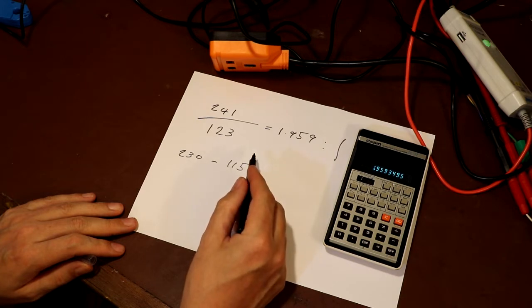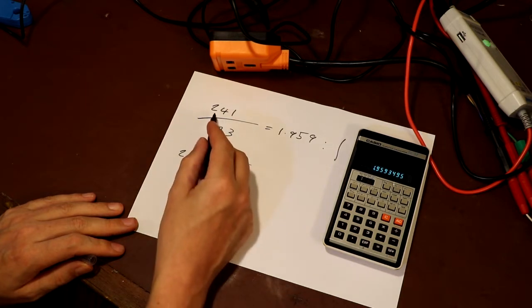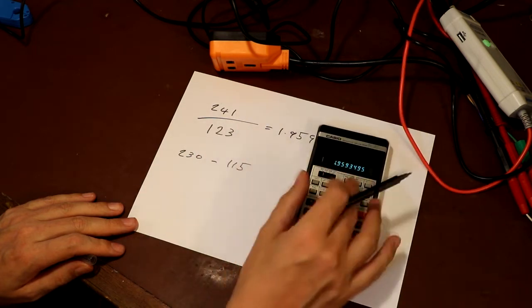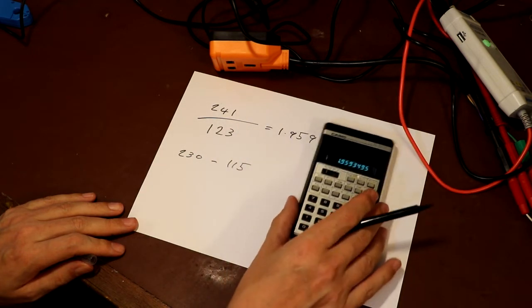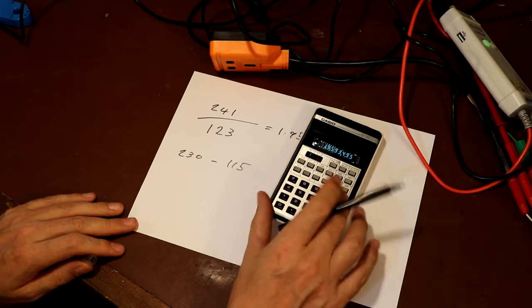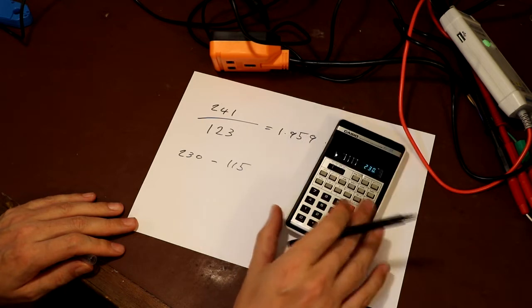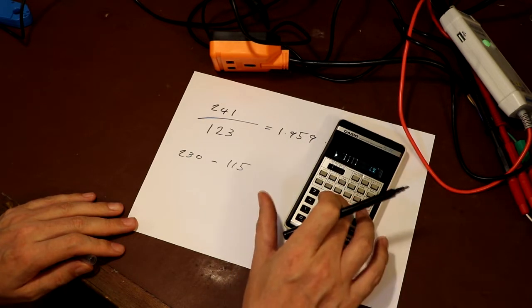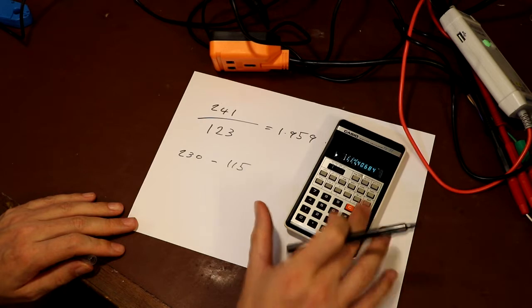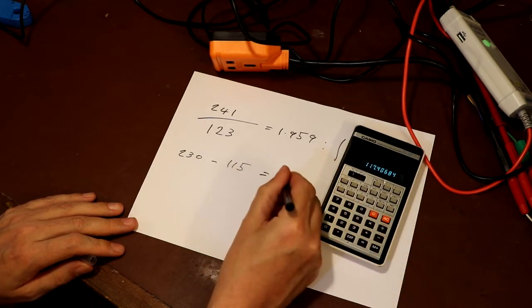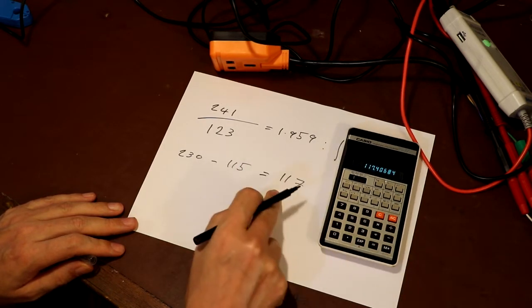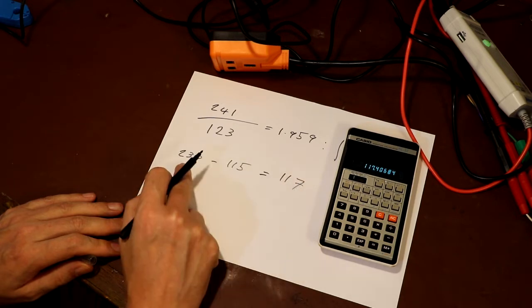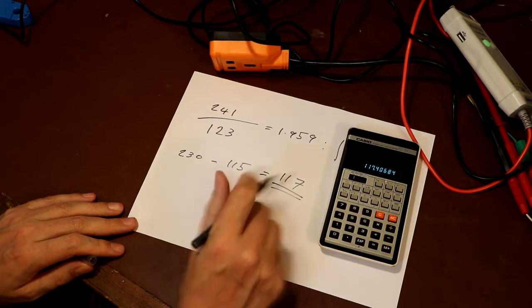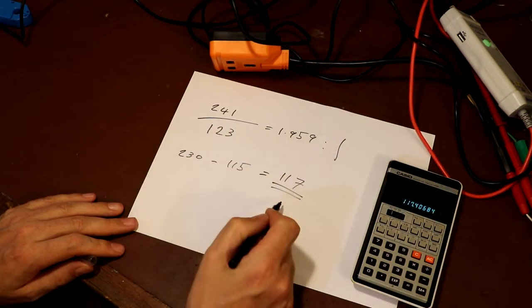Now unfortunately my main supply voltage is a little bit higher at 241, but what we can do is get a rough guess just using this transformer ratio here. So basically if we type in 230 volts, if our supply was 230, divide that by 1.959 equals. So I suspect it's more likely our transformer would be giving out 117 volts if it was actually connected to a 230 volt supply, and that's slightly more correct. But 122 volts unloaded, that's fine.